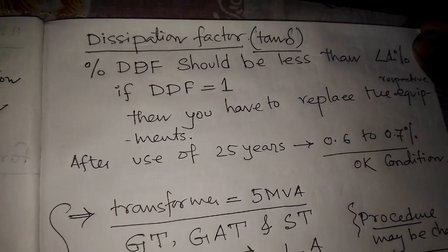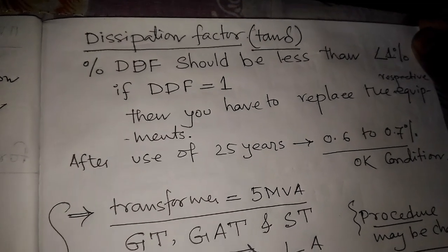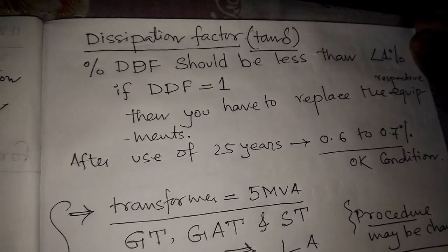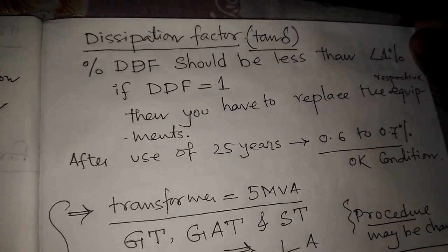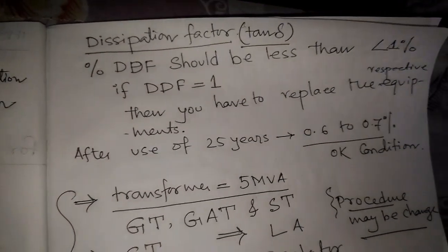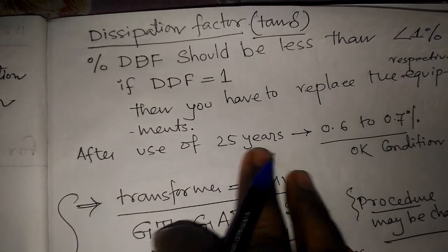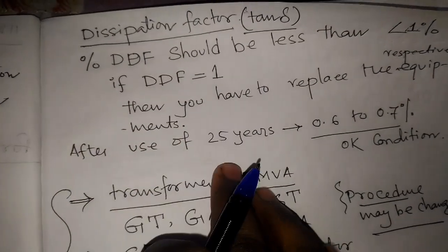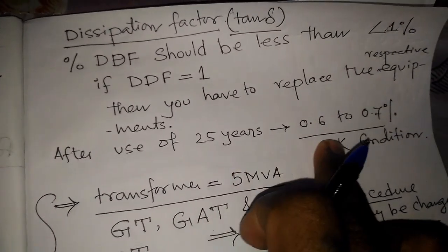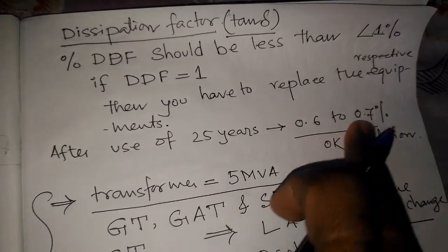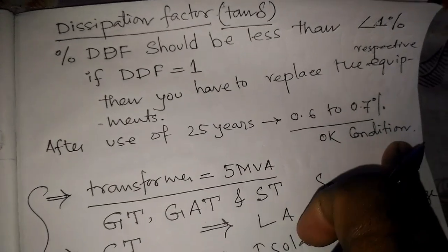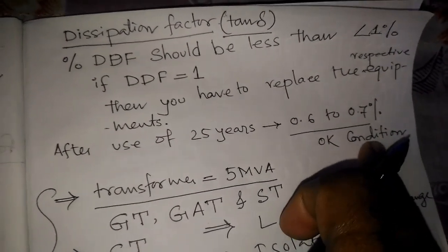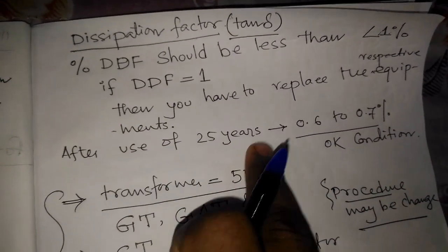If the DDF is 1 or above 1%, then you have to replace the respective equipment. After use of 25 years, if we do the Tan Delta test and get a result of 0.6 to 0.7%, the material or equipment condition is okay as per testing standards.